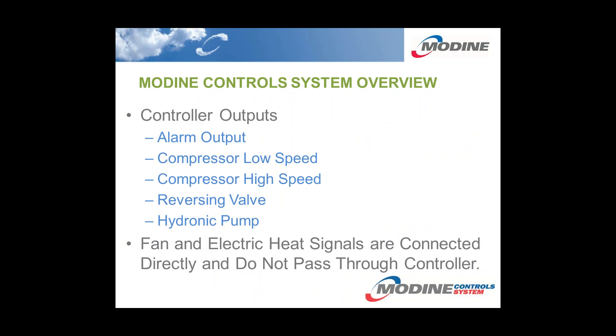For controller outputs, we have an alarm output that would go to an L-terminal on a conventional thermostat or to an alarm terminal on a water-to-water zone controller or boiler controller. The compressor low and high speed signals are also generated from the controller, as well as the reversing valve and hydronic pump if equipped. The fan and electric heat signals are connected directly to the fan and don't pass through the controller, meaning there's no variability on the fan speed or air volume. However, we do use ECM motors, so those will provide constant airflow for your application.